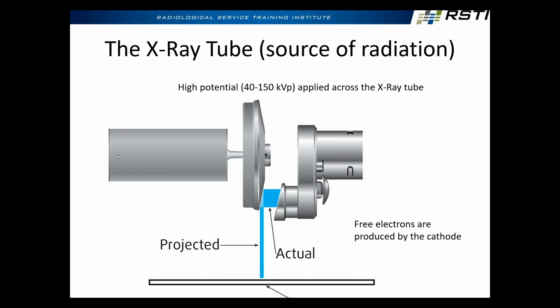And the focal spot is kind of not a misnomer per se, because it is where the electrons are focused. But a lot of people seem to think that it's focusing the X-rays. It's not, right? And a big part of the problem is the way this is always drawn. Because here they're comparing the focal spot, or the perception of the focal spot, from the perspective of the cathode and from the perspective of our image receptor.